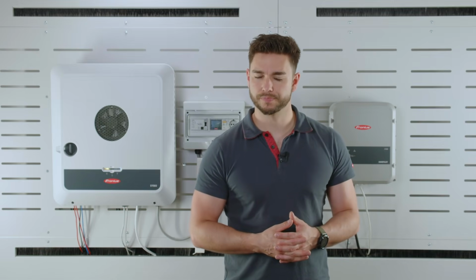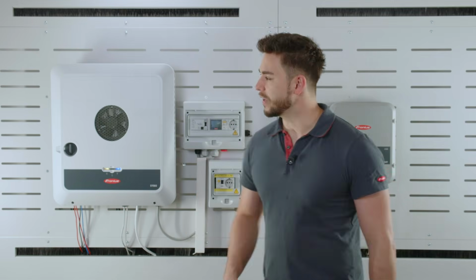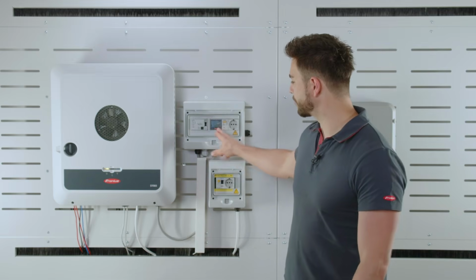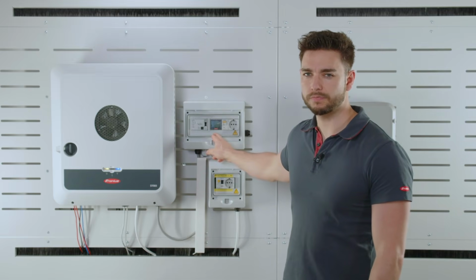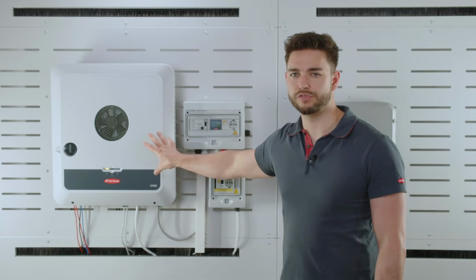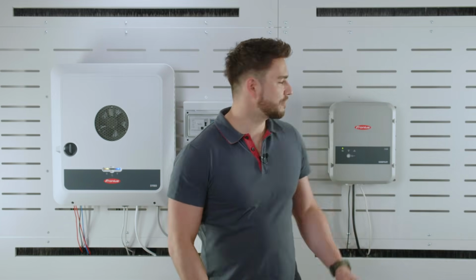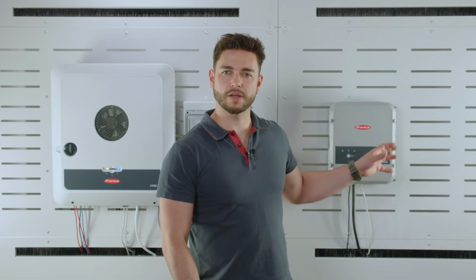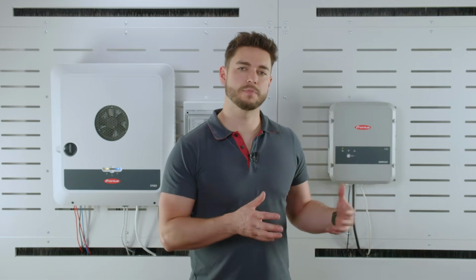It is a power regulator using the surplus energy of our PV system for our heating rods. In more detail, we have the surplus detected by our Fronius smart meter at the feed-in point. This is being sent to the Fronius inverter, and there we have the direct connection to the Fronius Ohmpilot, and we know exactly how much surplus energy we should give to our heating rods. And this is where we then have a higher own consumption because of this.